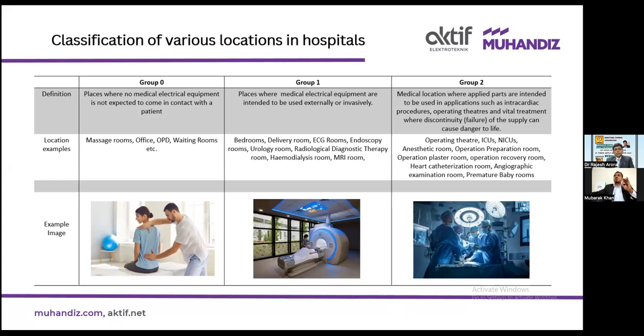Okay. Now, what is a Group 2 location? Medical locations where applied parts are intended to be used in applications such as intracardiac procedures, operation theaters, and vital treatment, where discontinuity of supply can cause a danger to life. So the difference between Group 1 and Group 2 is that in Group 2, if the power supply is disconnected, it can endanger the life of the patient. That is known as Group 2. Otherwise, the areas where medical electrical equipment is used are Group 1 locations. Examples of Group 2 locations are operation theater, ICU, NICU, anesthetic room, operation preparation room, operation plaster room, and all the other critical rooms in the hospital. Details are mentioned in the standard's Annex C, I think.